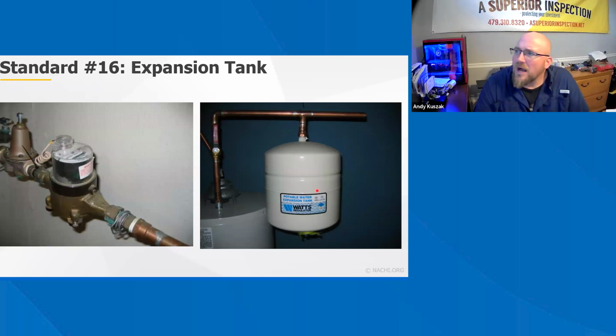So, expansion tanks. When a water heating appliance is connected to a water distribution system, migration of heated water into the water distribution piping is possible. In typical water distribution systems without some type of pressure relief, heated water will expand into the water service line and into the public main. If the expansion is not relieved or accommodated in the system, high pressure can develop that can damage pipe components and the water heater. For water service pipe sizes up to and including 2 inches, a device for controlling pressure shall be installed where, because of thermal expansion, the pressure on the downstream side of the pressure reducing valve exceeds the pressure reducing valve setting. A device for controlling pressure should be installed in a system that has a water heating appliance and a backflow prevention device, check valve, or other device, because thermal expansion will cause an increase in pressure.